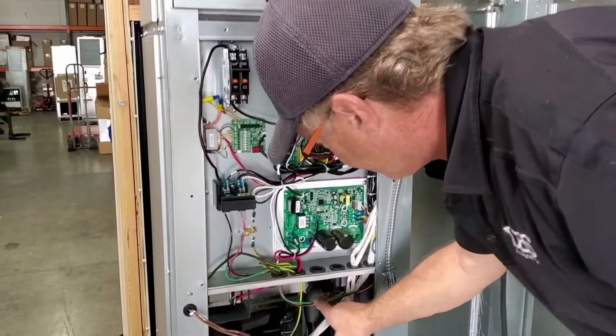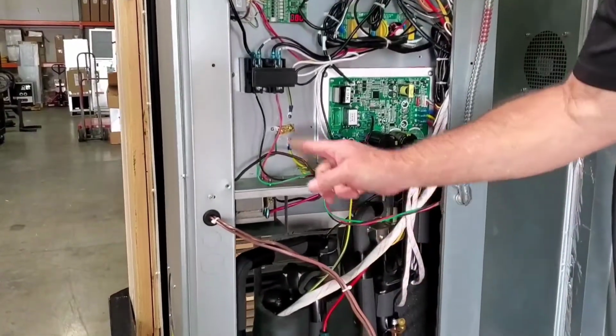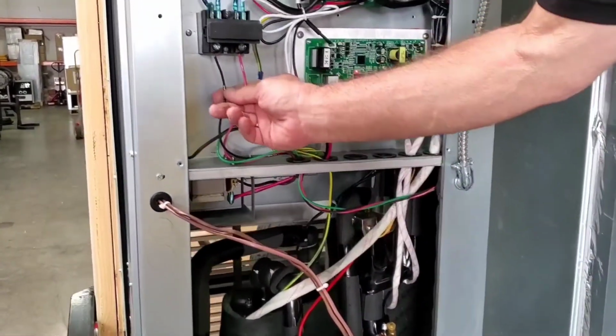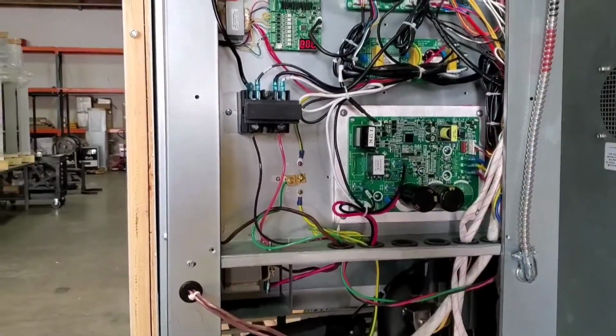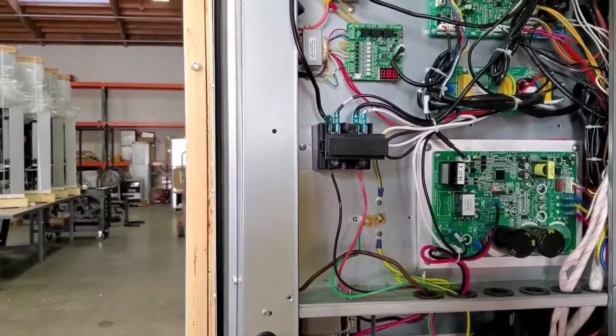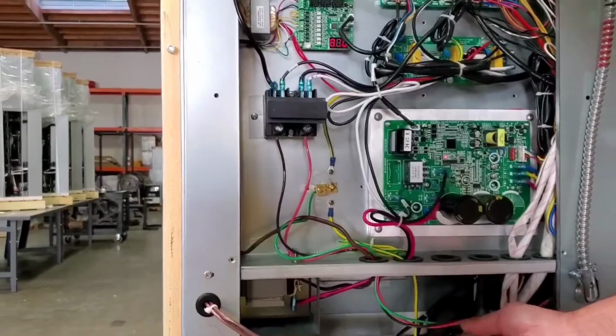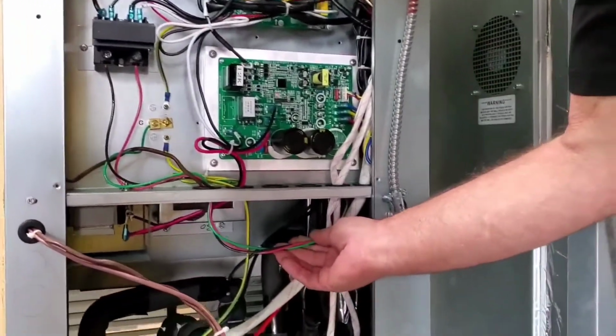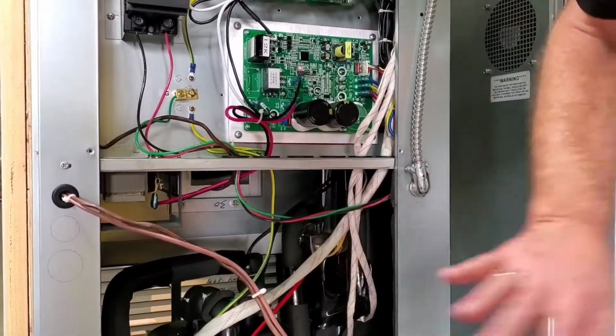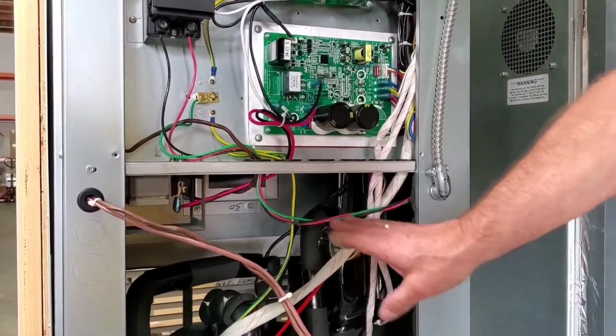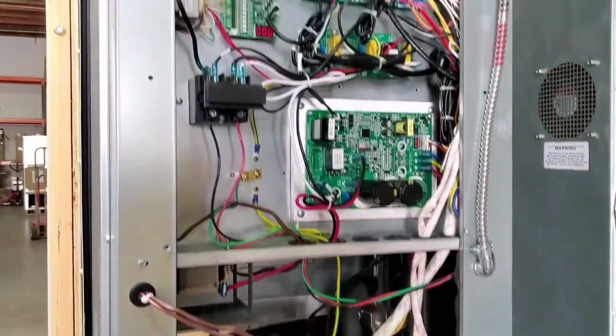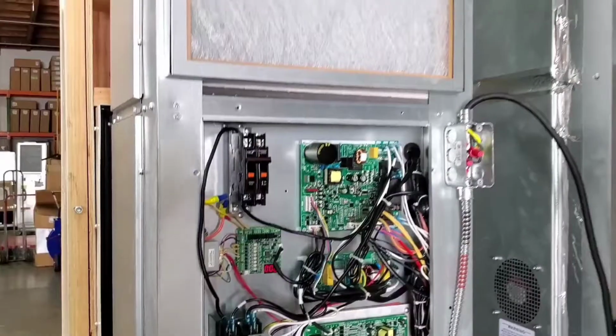So we've run the line underneath here, through this compartment, up and into the fused pole, or the pole disconnect. In some locations, you may need to run this in Romex, or you may need to run this in steel flex. In California, it's fine like this. Anything behind a cabinet is considered control wire, so this is legal. Some areas, I understand, you have to have that in Romex.